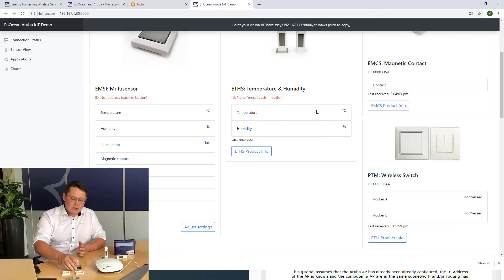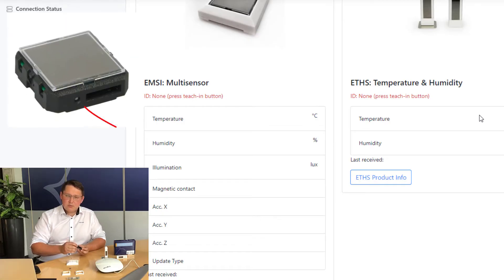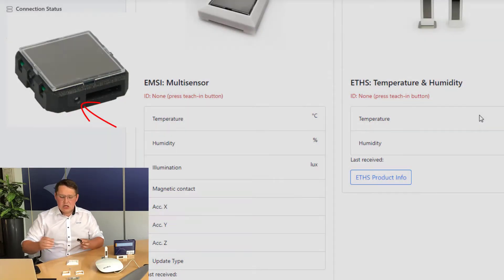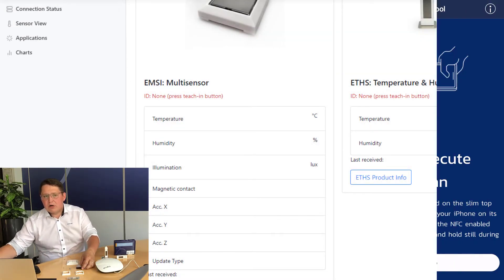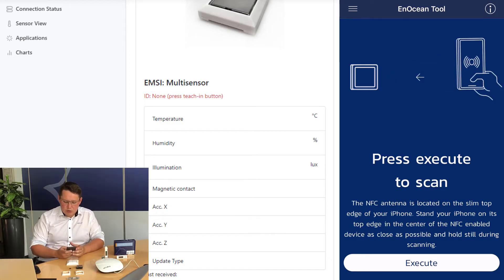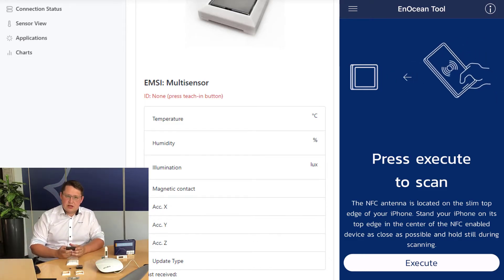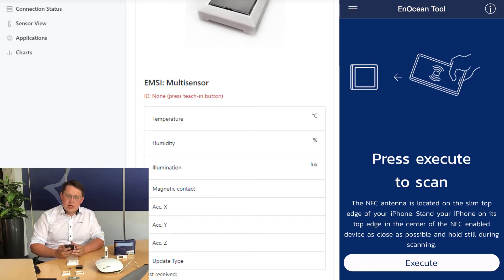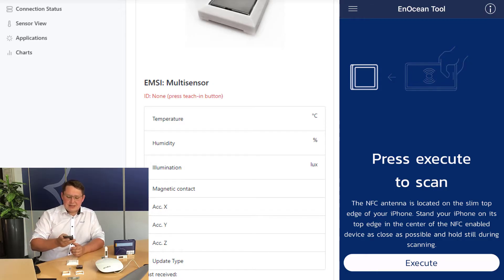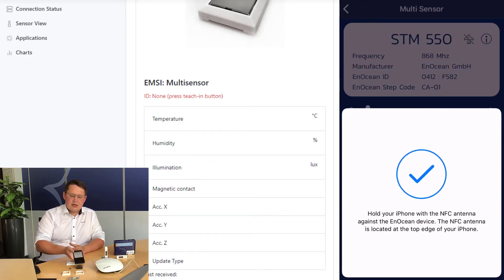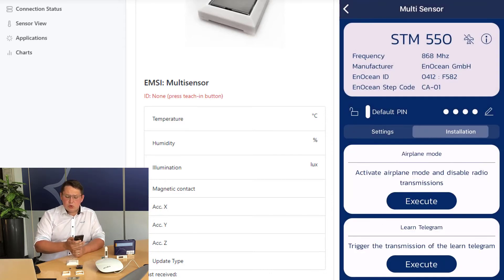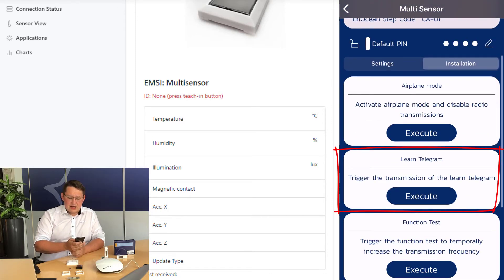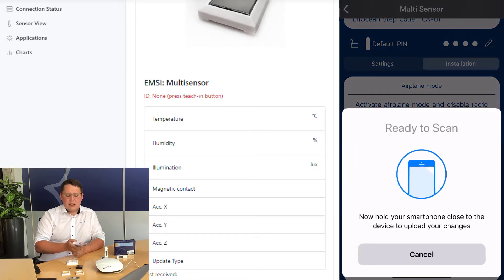In case of the multi-sensor, you have to press the learn button which is on the side, or you use our app which is called EnOcean Tool to trigger the learn telegram. You download the app from the app store, start it, scan the multi-sensor, go to installation and select execute when it comes to learn telegram.